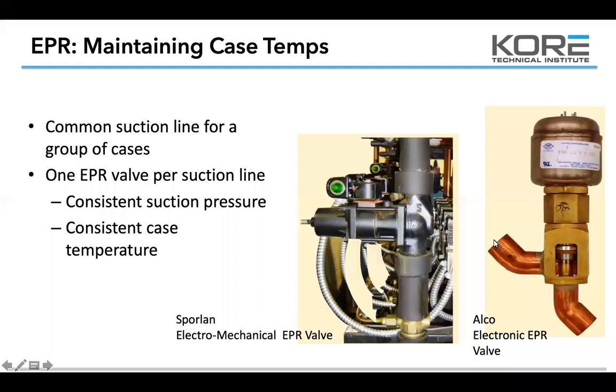This is a picture of an Alco EPR — we see a lot more Sporlan out there, but same concept. It looks at a thermistor, looks at the case through the controller, and has a board that drives that valve. These electronic valves are much more finite — some have thousands of steps — that's how precisely they can run that seat in and out to maintain the temperature they want.